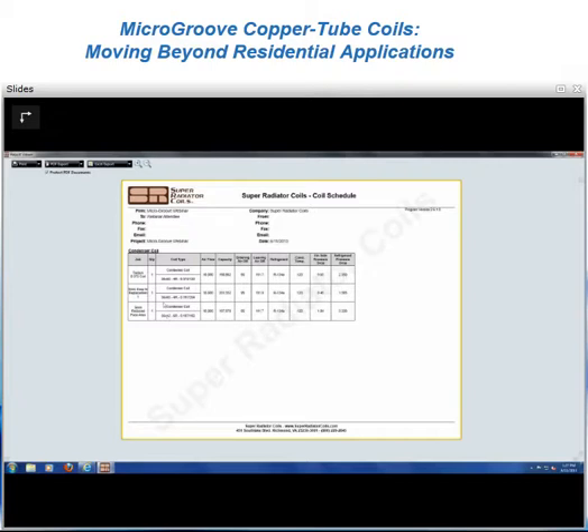So the shorter coil at the bottom, 42-inch fin length compared to 60-inch fin length. What we've done with this coil is now we've decreased the copper weight still by 52%. The refrigerant volume is down by 51%, so we haven't lost either one of those benefits, but we have a coil that's in a much smaller footprint. And there's a lot of things you can do system design-wise to take advantage of that.